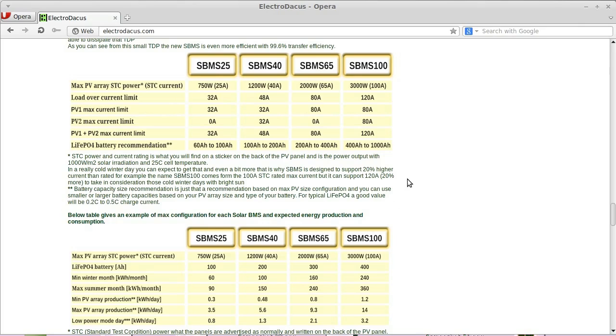Even though each PV input, for example on the SBMS 100, can handle 80 amps max, the sum of the two should not exceed 120 -- this is the overcurrent protection limit. So you can have a larger array on PV1 and a smaller one on PV2, as long as the total is under 120. So about 3 kilowatts of solar PV panels for SBMS 100 is possible this way.